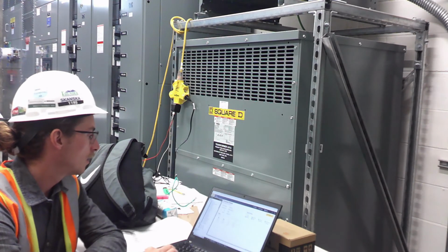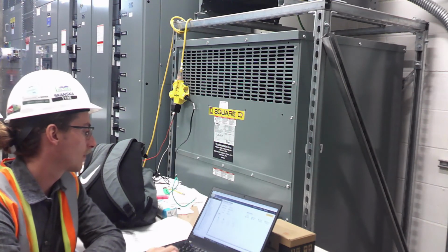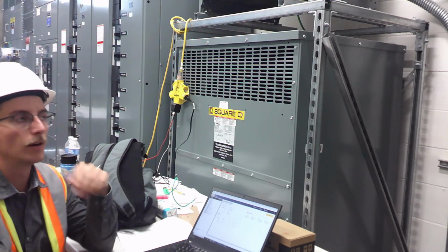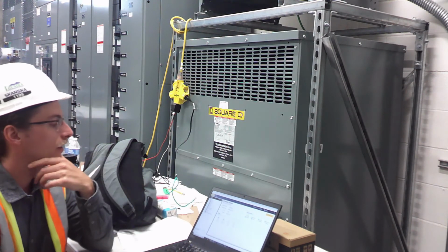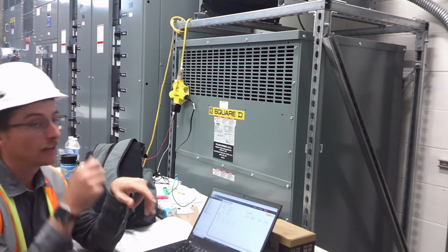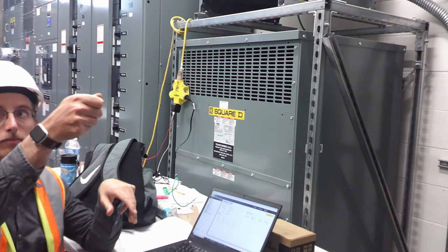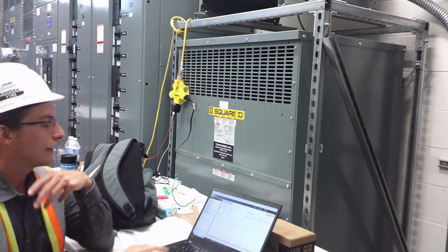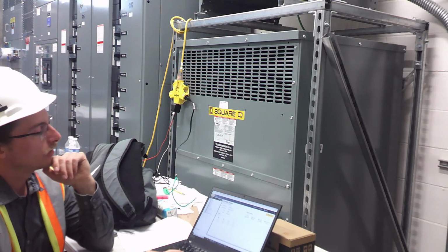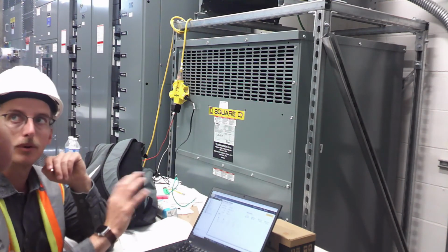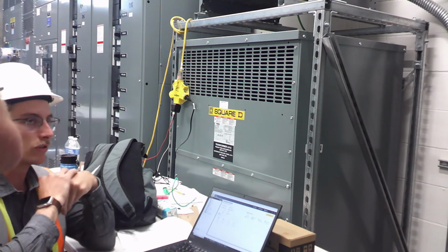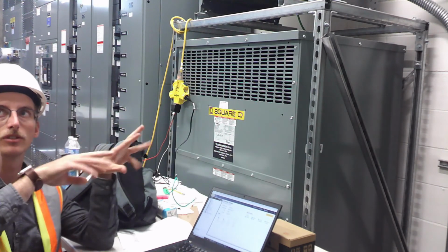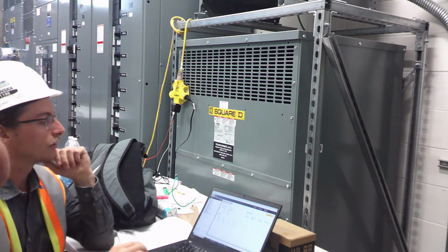Oh, one other thing. If you add a device onto the network, you plug in a switch, add a controller, or if you move a switch to a different port, it'll think it's a new switch. So, adding devices, you have to come up here and hit discover, and basically the area controller will send out a message to all the bridges and say, start telling me if you have new devices on you. And it will take a little while.